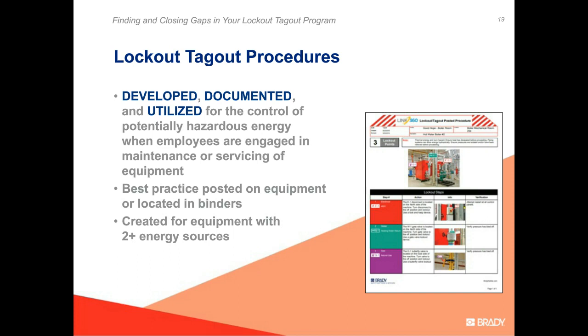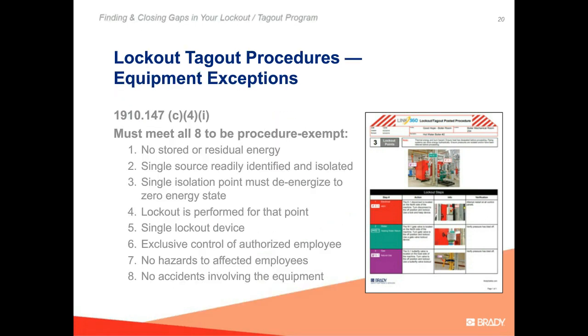You do not need to create lockout tagout procedures for equipment that meets all of these exceptions. It has to meet all eight, but when looking around your facility for equipment that needs a machine-specific procedure, it's a good reference to see if it has only one energy source, like a laptop computer with a single 120 volt plug. You can lock it out with one energy source and it completely isolates the energy. That's something exempt from having its own machine-specific procedure.